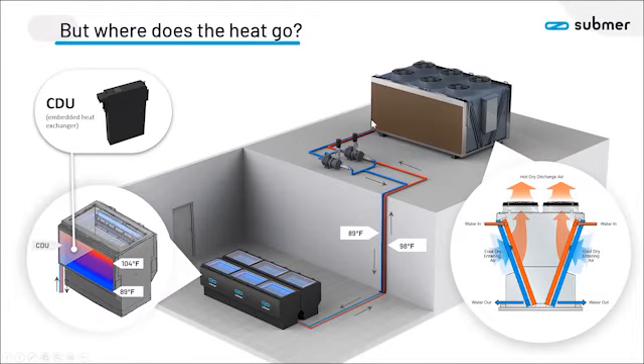If you're in a warmer environment where freezing isn't a risk, I'd just run all water, or water with a little glycol to make it work nicely — a very efficient cooling medium. Then there are just the fans to move air across the coils, across the heat exchanger, and that's extremely efficient.